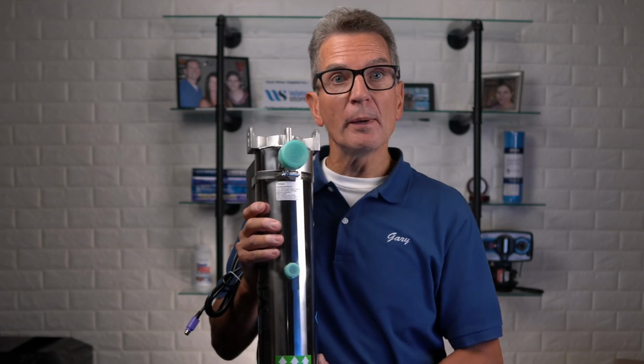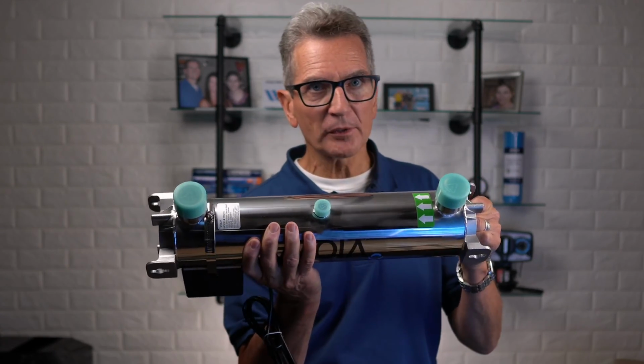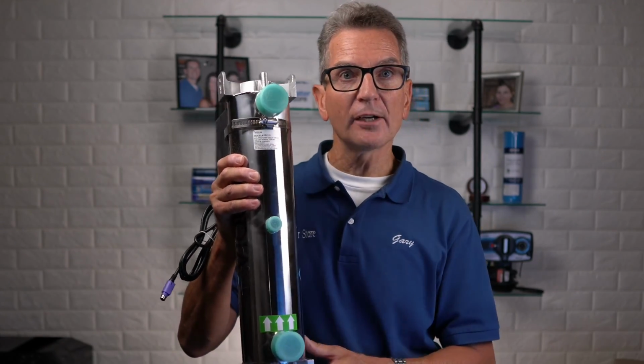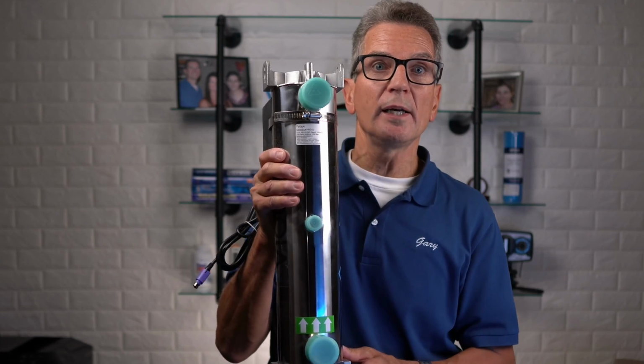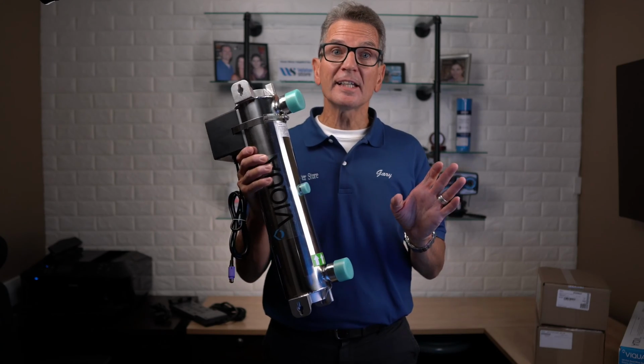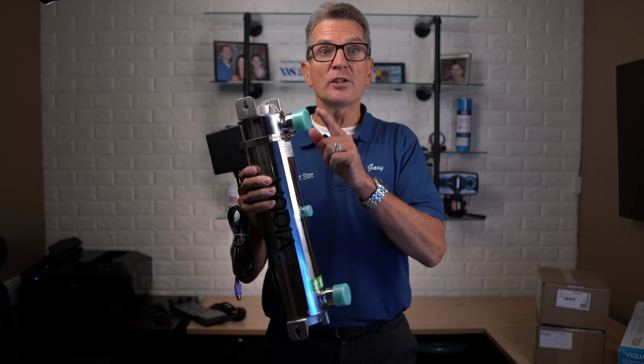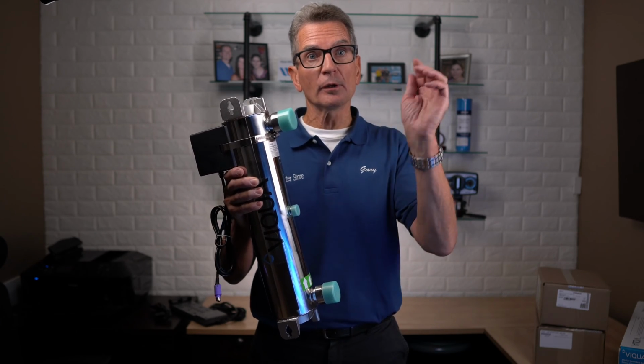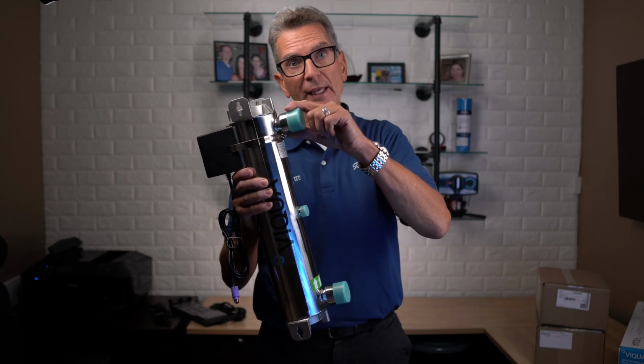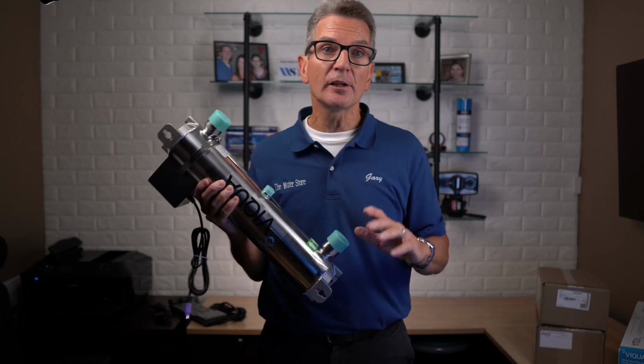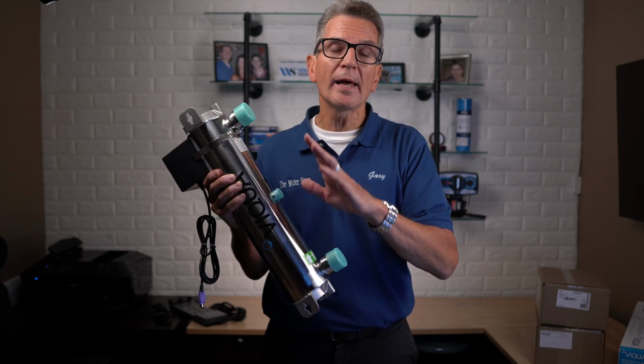Now these have to be mounted vertically. They cannot be mounted horizontally. And you can see it has arrows on it here, which shows you which way it should be orientated. And the other thing to keep in mind during installation of these is you have to have at least 12 inches of copper before you switch over to PEX. You can't have PEX coming right up to here because the ultraviolet light shining on that PEX will degrade it over time.